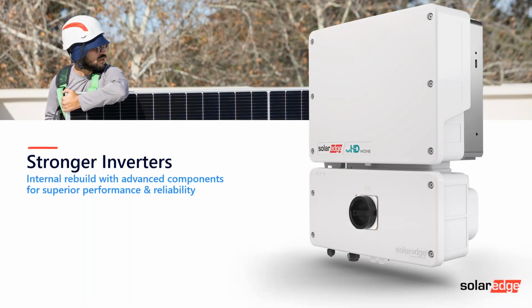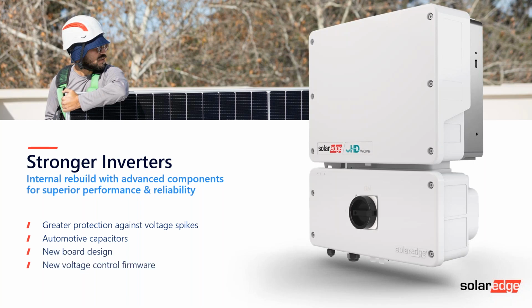I guess to address a bit of an elephant in the room, I think it's fair to say our older model HD-Wave inverters haven't behaved or performed as well as we'd like. And one of the things that we've invested a huge amount of time in over the last couple of years is rebuilding the inverters completely, but also the firmware, to help control the voltage spikes that we're seeing that drive potential flaws in the system.